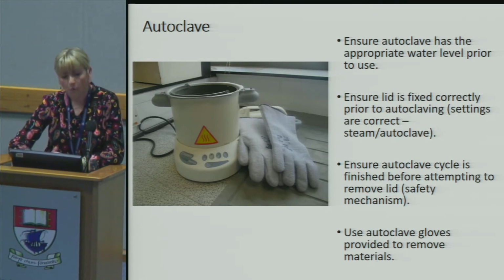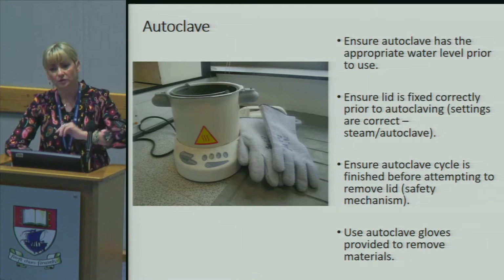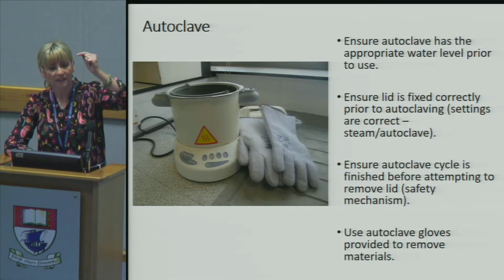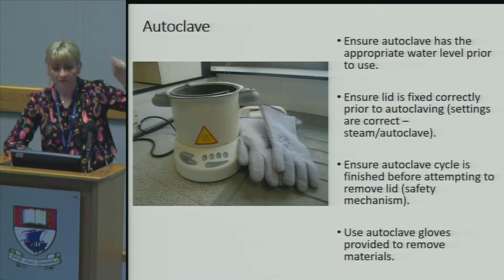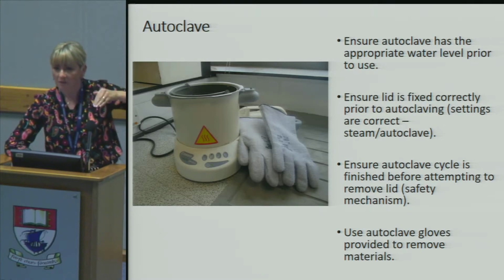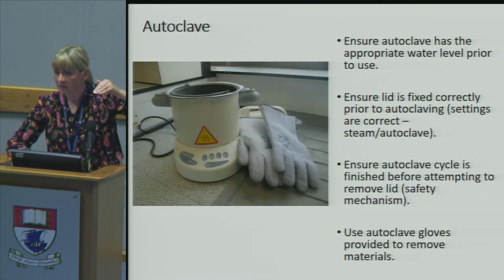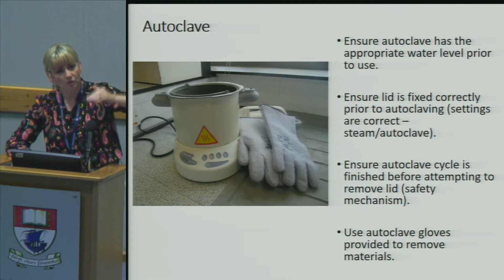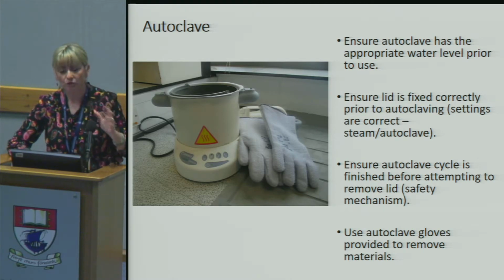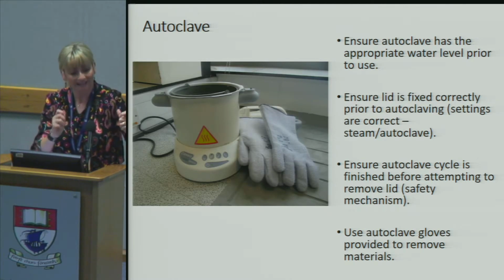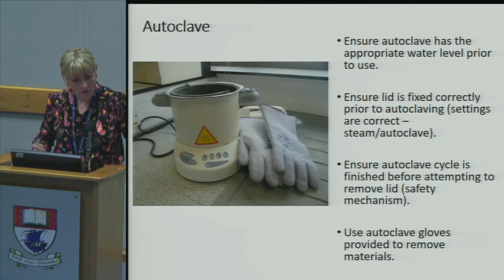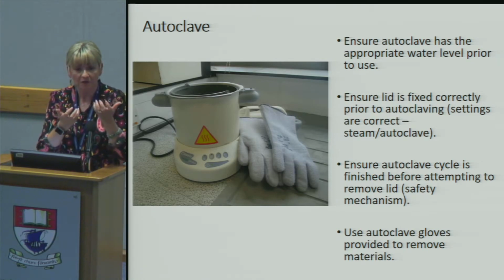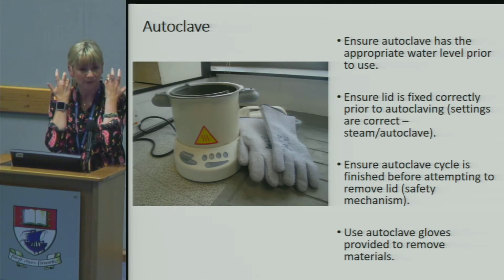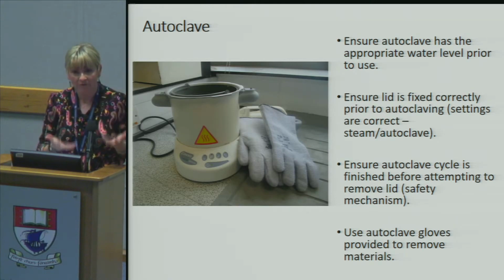But in addition, as you all know, pressure rises in an autoclave, and the valve will lift. So even though your cycle is finished, the pressure won't have reduced immediately in that autoclave. So the valve will stay lifted and will drop when the pressure comes down. If you try, and some people are strong, some people can force a lid to open even though it's not supposed to, that's going to be very dangerous, because under the pressure the liquid will bubble up at 137 degrees and land on you. So it will come out and destroy you. So you have to be very careful.